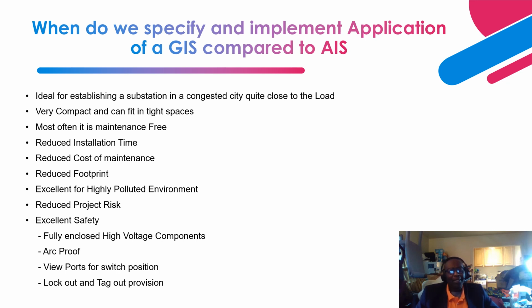Your best choice is gas insulated switchgear, which has a smaller footprint and comes in the form of compartments. Talking about the safety part, in a highly densely populated city, the GIS offers more safety compared to an AIS. In terms of reliability too, the GIS has a higher reliability than the AIS. Next is that it is very compact, and that is perfectly true, because I made mention that it comes in the form of compartments, in the form of modules. That's how it is shipped before it is assembled in the field.